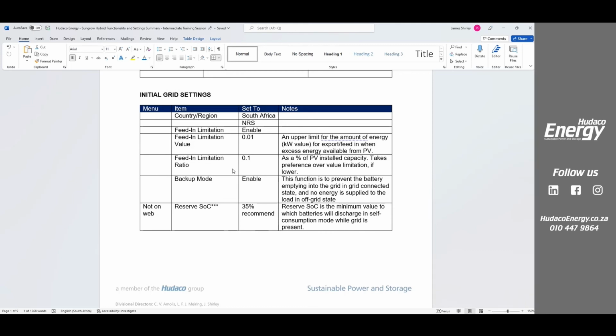Okay, so once you do that, the little blue light on the front of the inverter will go from flashing to solid, and it'll wait for 60 seconds. The reason it waits for 60 seconds is that's what is required by our national standard. Then you'll hear the relay click a few times, and it'll come live. In other words, it'll take over the load. Okay.